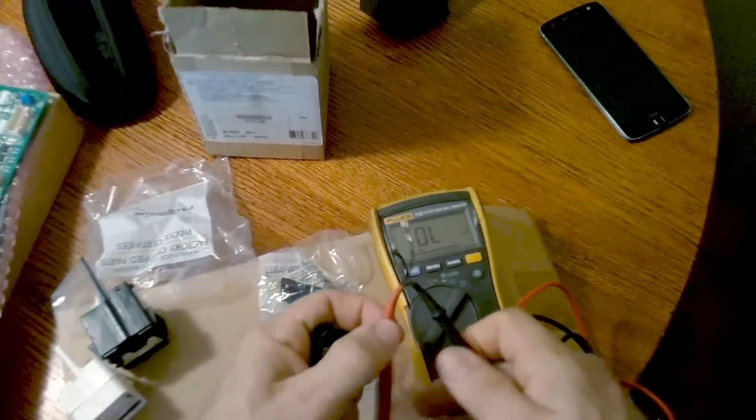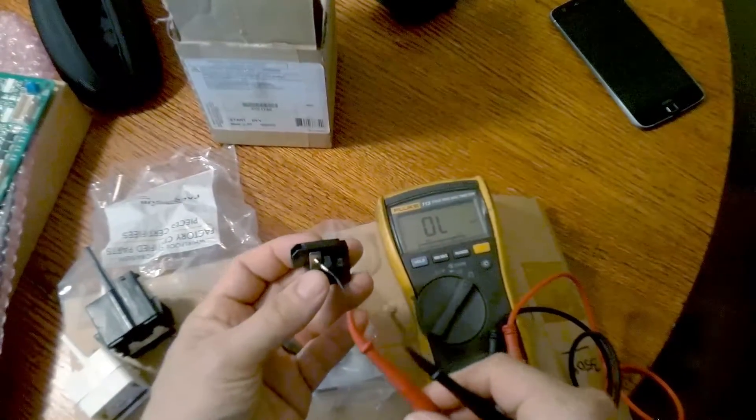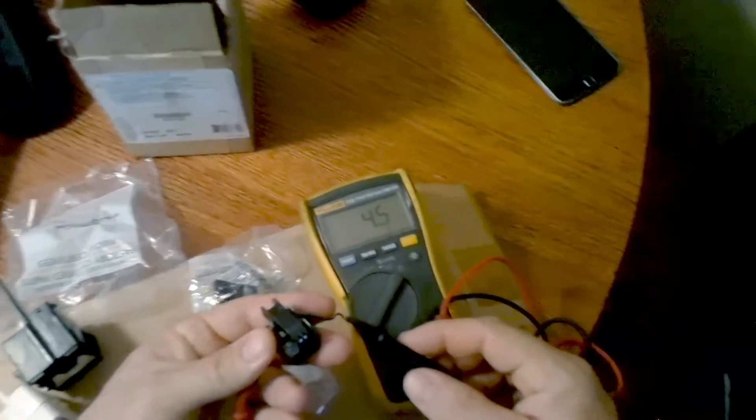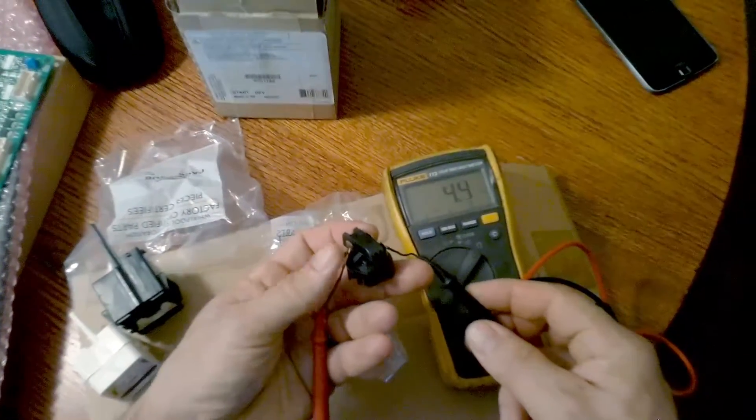This is a different type of relay. You test it the same way but you go to your left and your right prong and you should read like 4.5 to 4.9.